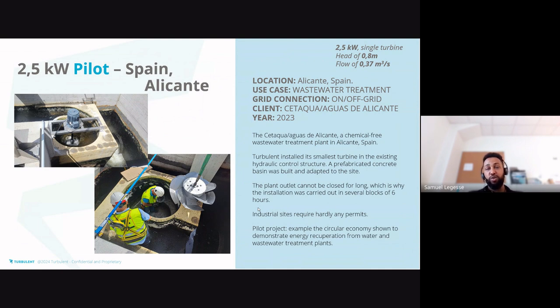The third option we use is on or off-grid, meaning you can generate following the grid frequency or behavior, but whenever the grid is down, you can switch to off-grid mode. The UPS device we use will disconnect the turbine from the grid and can give energy to your mini grid or facility you'd like to protect whenever there's a grid outage or load shedding. This is one of the main separating points for these small turbines in wastewater treatment plants.